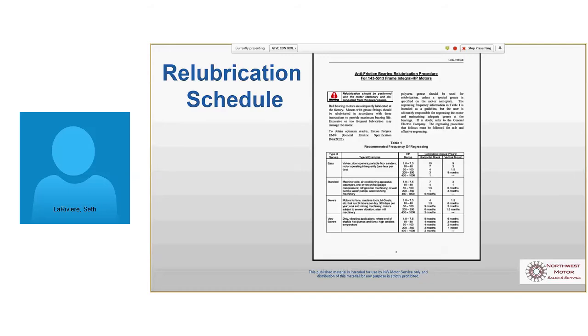So a lot of guys, their regreasing schedule may be quarterly. They'll go by and regrease motors, give it a couple of shots. They really don't know how much they're pumping in, how many ounces of grease is going inside, and how often. So you can see, if you've got a lot of contaminants, you want to purge that grease pretty often just to get the old crappy grease out and get in fresh grease. But if your grease is clean and it's cool and not contaminated, you're looking at about a year and a half before you really need to even regrease the motor.